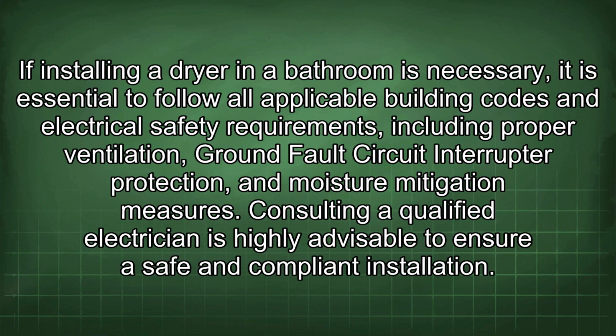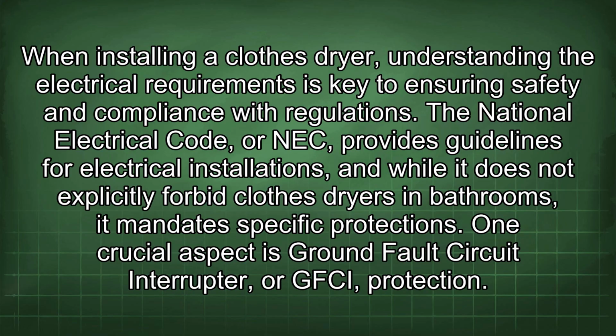If installing a dryer in a bathroom is necessary, it is essential to follow all applicable building codes and electrical safety requirements, including proper ventilation, ground fault circuit interrupter protection, and moisture mitigation measures. Consulting a qualified electrician is highly advisable to ensure a safe and compliant installation. When installing a clothes dryer, understanding the electrical requirements is key to ensuring safety and compliance with regulations. The National Electrical Code, or NEC, provides guidelines for electrical installations, and while it does not explicitly forbid clothes dryers in bathrooms, it mandates specific protections.